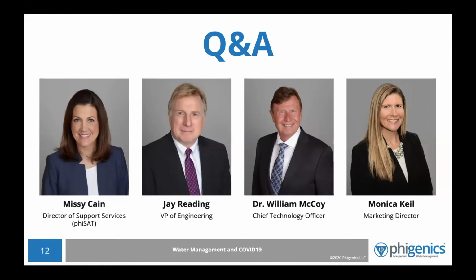Thank you, Monica. The key here is verification of your control measures. For potable water you're basically relying on one of three approaches: the disinfectant the city supplies, adding supplemental disinfectant, or heating the water. Verification means taking the actual steps to make sure what you're trying to do is being accomplished, so confirm the water is hot enough and that there's enough disinfectant in it.